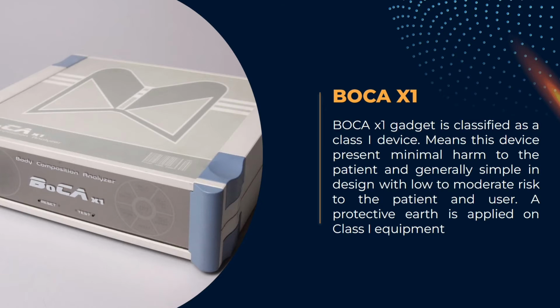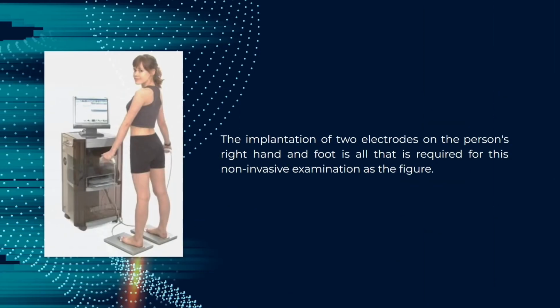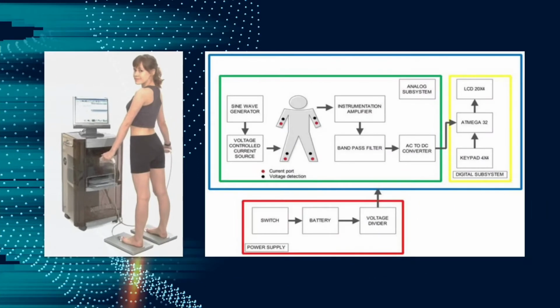A protective earth is applied on class 1 equipment. The implantation of 2 electrodes on the person's right hand and foot is all that is required for this non-invasive examination, as in the figure. So how is the flow system of this device?